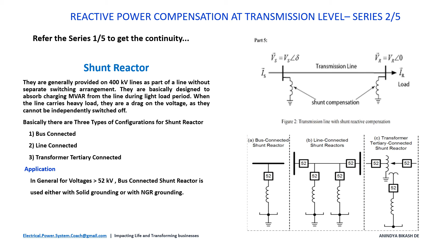Basically there are three types of shunt reactor configuration. One is bus connected, one is line connected, and the third is transformer tertiary connected. You can see the figures on the right side: the bus connected shunt reactor, the second one the line connected shunt reactor, and the third one the tertiary connected shunt reactor. Usually for voltages more than 52 kV, a bus connected shunt reactor is used, either with solid grounding or with neutral grounding. There is a specific purpose of neutral grounding the shunt reactor, for arc suppression, which we can discuss in a separate slide in future.